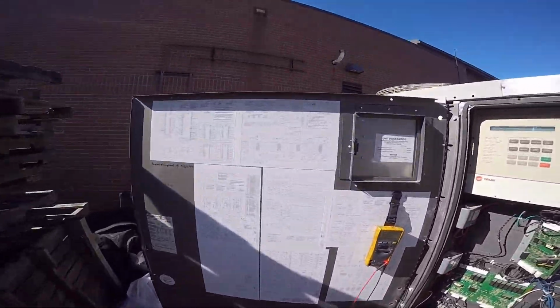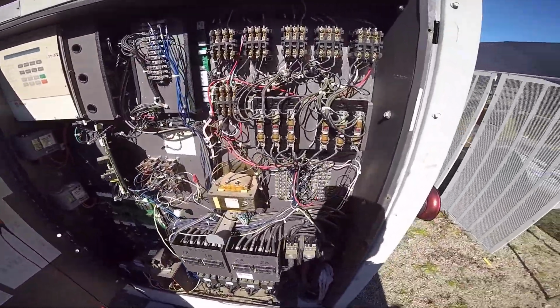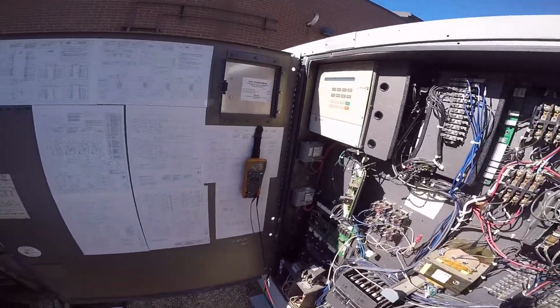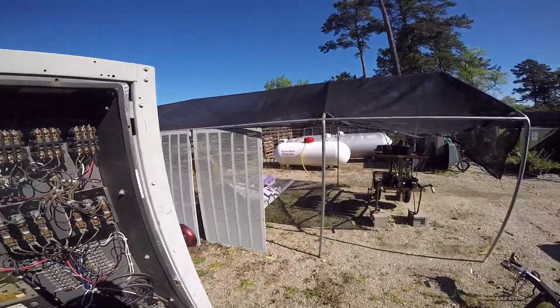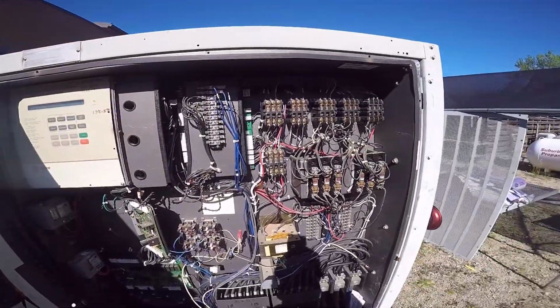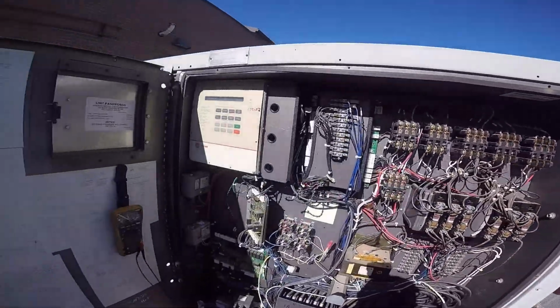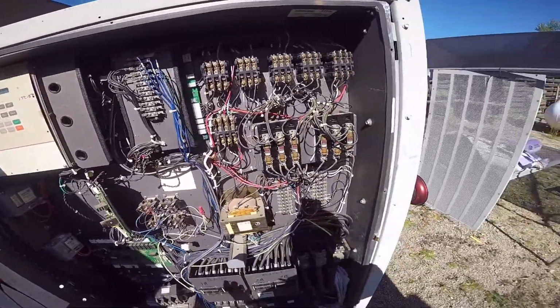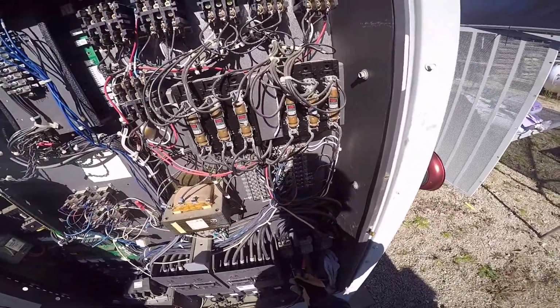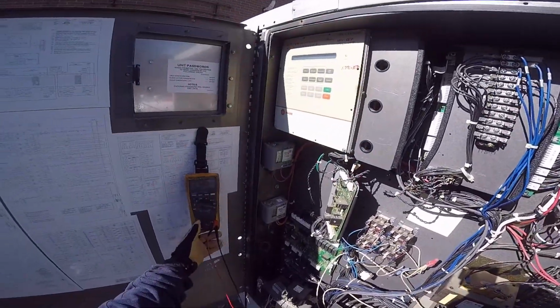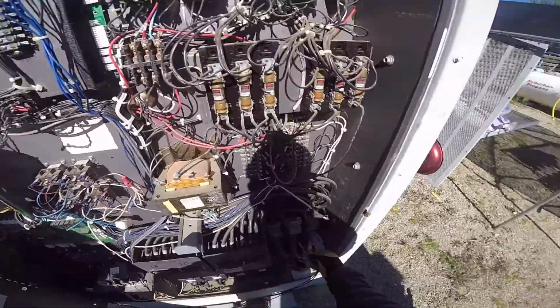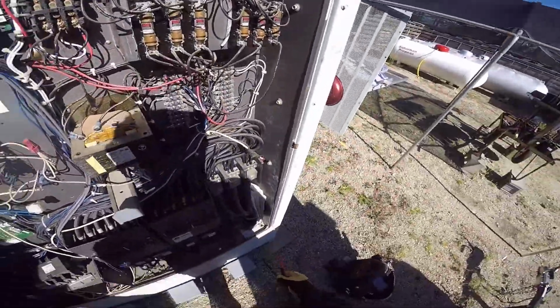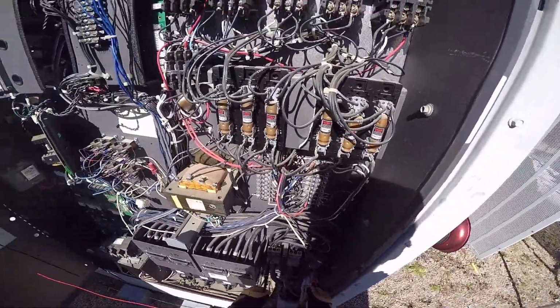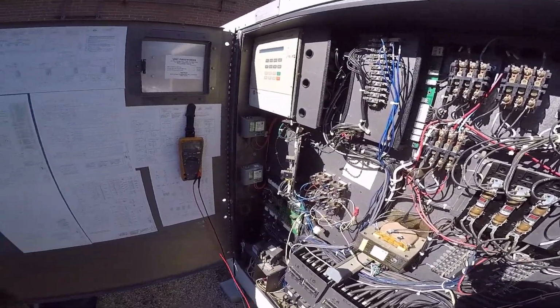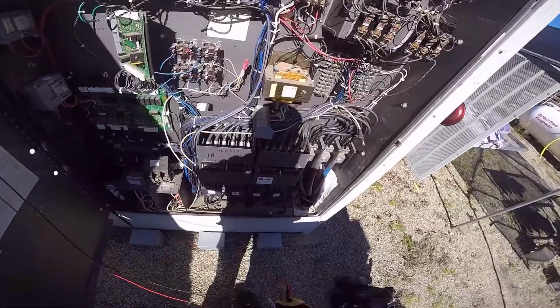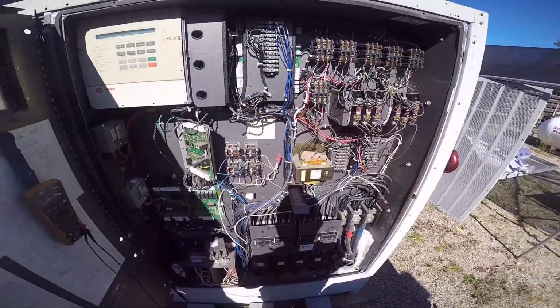So we'll cover the electrical part of the PM. For me, the first thing I do is check the incoming legs of power. This is a campus that I know runs on 208, which is not common - it's usually 460. So first we go 1 to 2, and we got 210. Then 2 to 3, 210. And then 1 to 3, 211. So our incoming power is clean, and we know all the legs are correct.